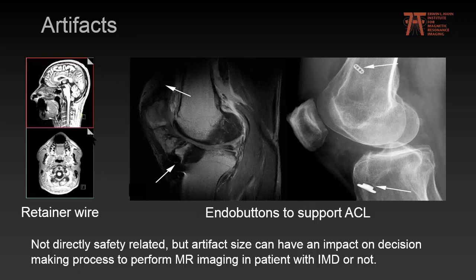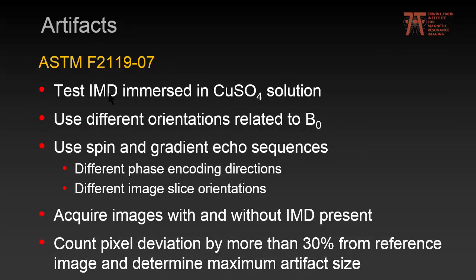Briefly on artifacts — for example from retainer wires or endo buttons supporting an artificial ligament. While not directly safety-related, artifact size can have an impact on the decision whether to perform imaging. The test standard recommends immersing your device in copper sulfate solution, using different orientations relative to B0, and acquiring images with and without the implant using spin and gradient echo sequences, changing phase-encoding direction and slice orientation to find the maximum artifact size.